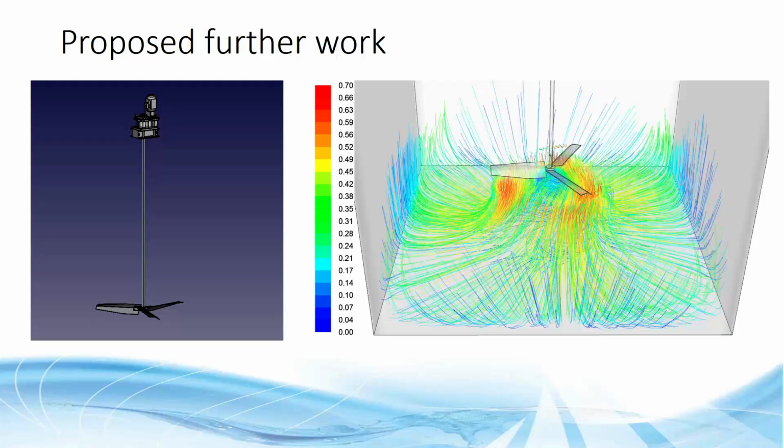The issue is that this is a current structure and it has to remain in operation. So I discussed it with the client if this would be suitable. We then determined that it would be impractical to adopt and it would be problematic in terms of health and safety. So we found a different solution, which is the use of a large blade propeller that could be installed whilst the chamber remains in operation.